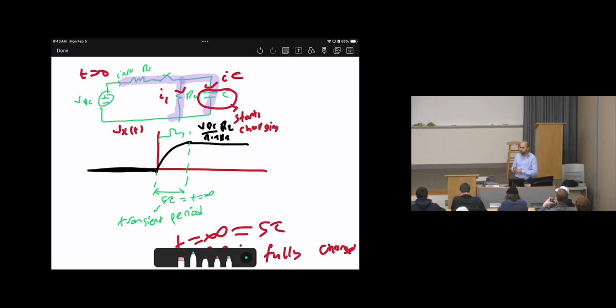Even if you have a mobile generator and try to use, for example, some motors or a pump for inflatables, if you turn on that pump initially, you will see the generator speed moving like this, because it will absorb a high amount of current at startup, which is called high startup currents. The main reason is that the equivalent inductance will take time to be fully charged. When it is fully charged, it will work as normal without any problems. So we are worried about what's happening during this 1 second or 1 millisecond. We need to make sure the system will be stable and there will be no problems in our operation. That's why we are studying this.